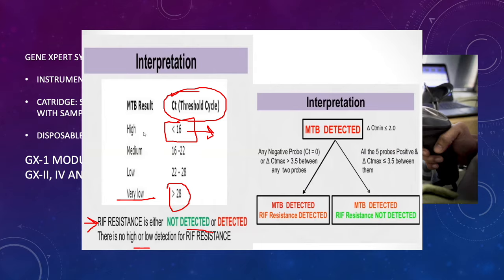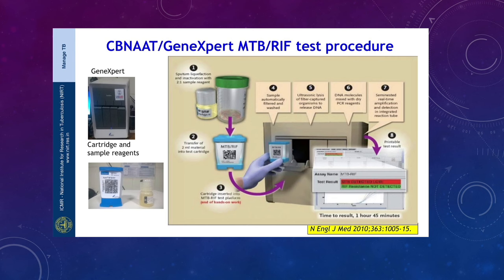The system consists of the module, the machine, and the cartridge. There is a reagent mixed in a 2:1 ratio into the sputum or body fluid sample. It is then entered into the cartridge. Once the cartridge is inserted, all the cleaning, filtering, washing, and processing is done inside the machine — so there is no exposure of the healthcare worker. Inside the machine, it lyses the DNA, captures it, amplifies it using semi-nested real-time PCR, and detects results visible on the computer screen, showing whether MTB is detected or not detected, and rifampicin detected or not detected.